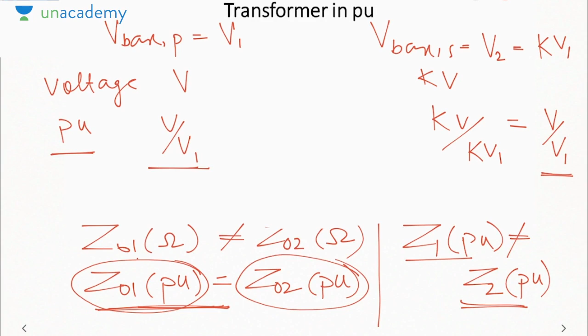So per unit voltage is the same on primary and secondary, per unit impedance is the same, and per unit MVA is the same, so per unit current will also be the same. Each per unit quantity remains the same on the primary and secondary winding of the transformer; it does not change when we go from primary to secondary or secondary to primary. So since these quantities remain the same, the turns ratio does not matter anymore, and we can remove the turns ratio of the transformer. So if we remove the turns ratio, what happens then?